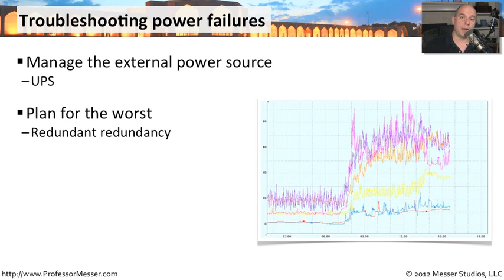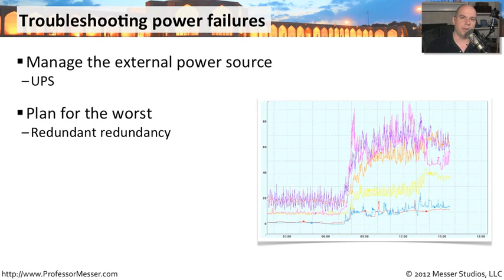We can even run those power connections to two separate power sources. And if you lose one of those power sources, or that power supply itself happens to fail, you have a completely redundant power supply in that device that can handle the entire load of that machine all by itself. That way we can be assured that if there's any type of physical problem or any type of problem with a particular power source, we will still be up and running.